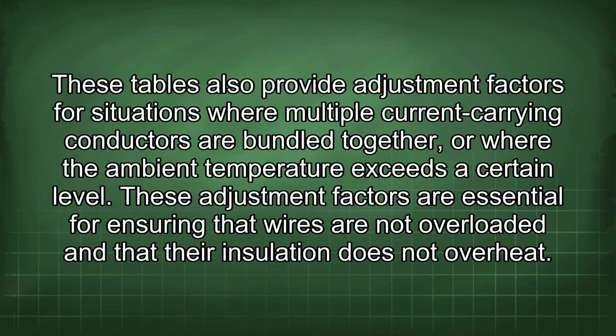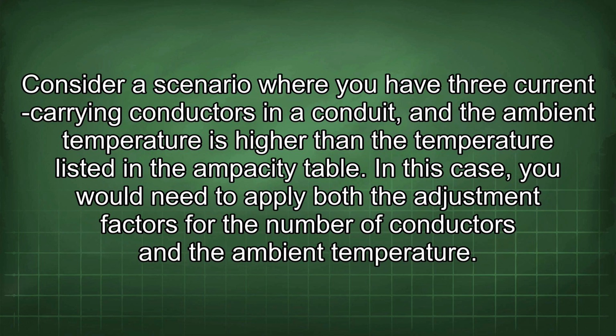These tables also provide adjustment factors for situations where multiple current-carrying conductors are bundled together, or where the ambient temperature exceeds a certain level. These adjustment factors are essential for ensuring that wires are not overloaded and that their insulation does not overheat. Consider a scenario where you have 3 current-carrying conductors in a conduit, and the ambient temperature is higher than the temperature listed in the ampacity table.